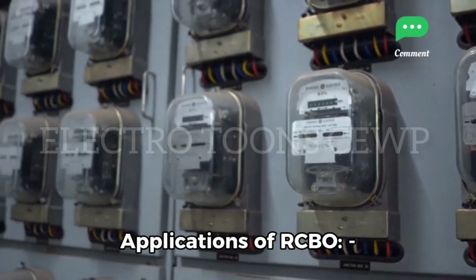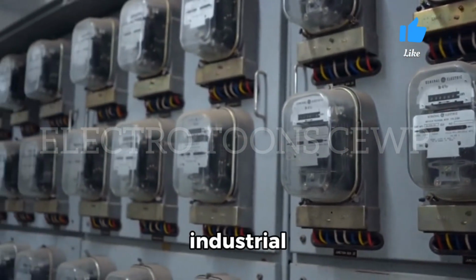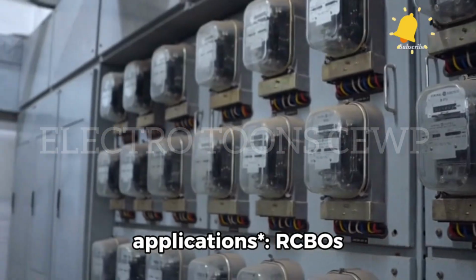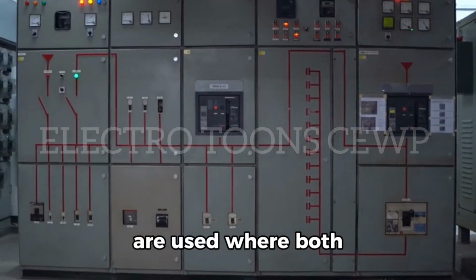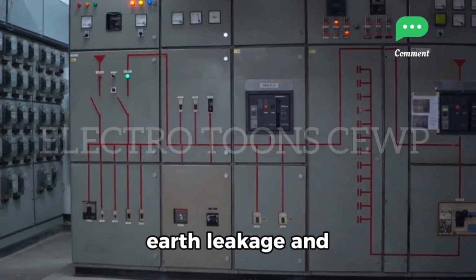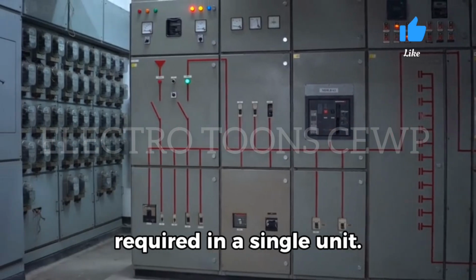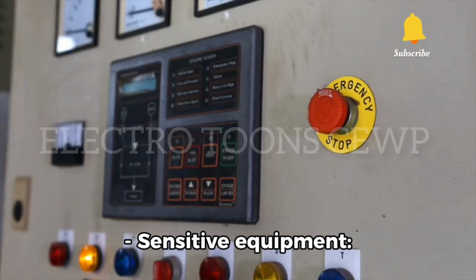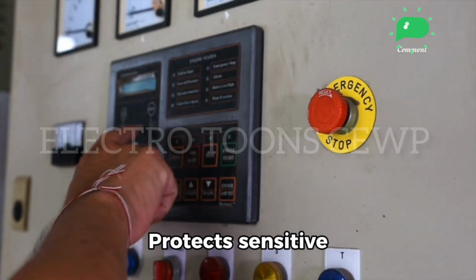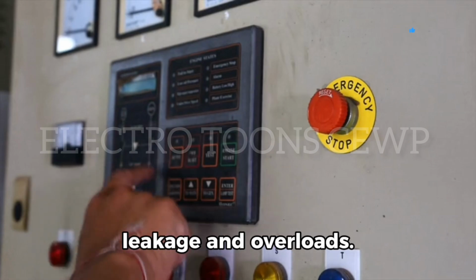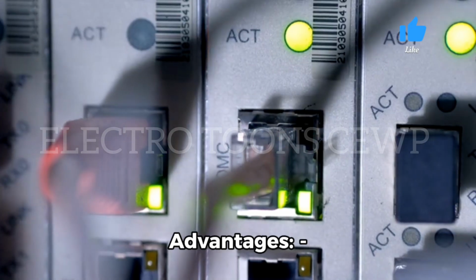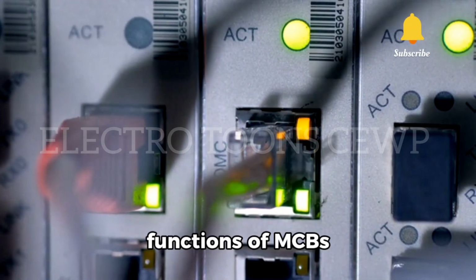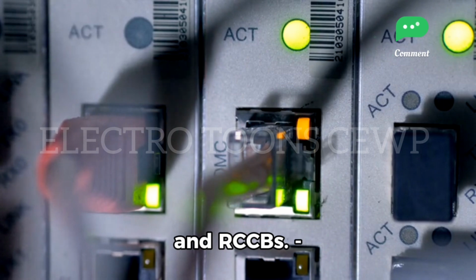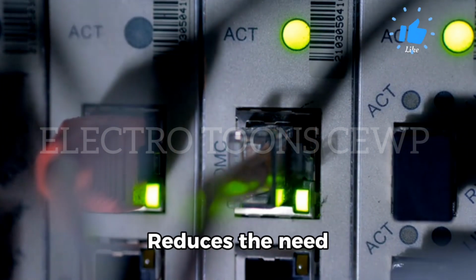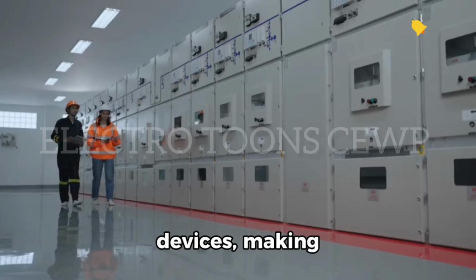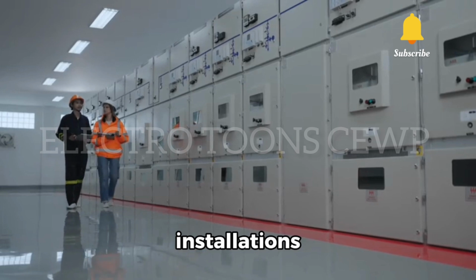Applications of RCBO: residential and industrial applications. RCBOs are used where both earth leakage and overload protection are required in a single unit. Sensitive equipment: protects sensitive equipment from both leakage and overloads. Advantages: combines the functions of MCBs and RCCBs. Reduces the need for multiple devices, making installations simpler and safer.